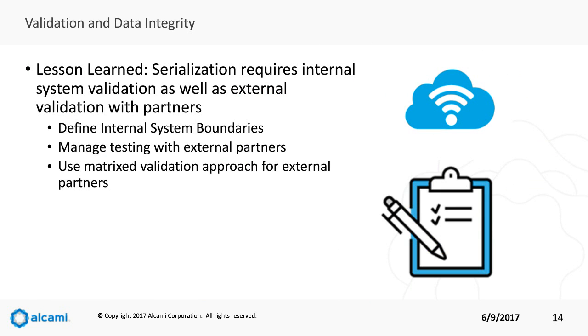Now that we've reviewed some of the complexities of serialization, let's talk about validation. Serialization is unique because it requires internal system validation as well as external validation related to the connection and data exchange with trading partners. Internal validation of your serialization systems sets the foundation for a successful overall plan. This starts by defining the intended use of the system, defining system boundaries, and building a test plan.